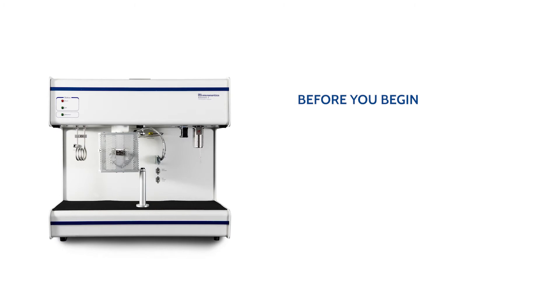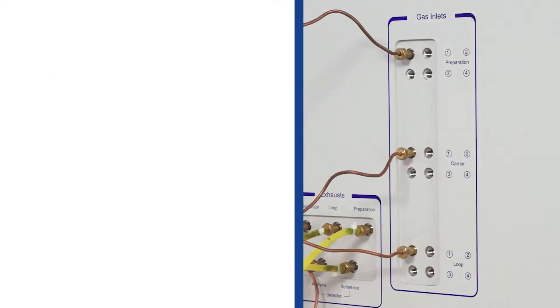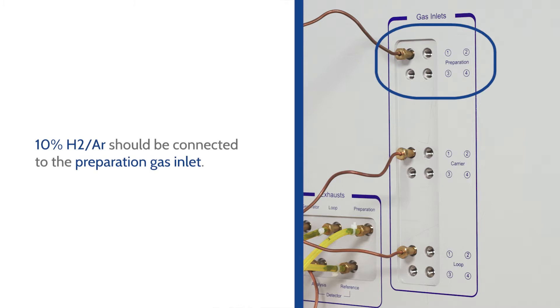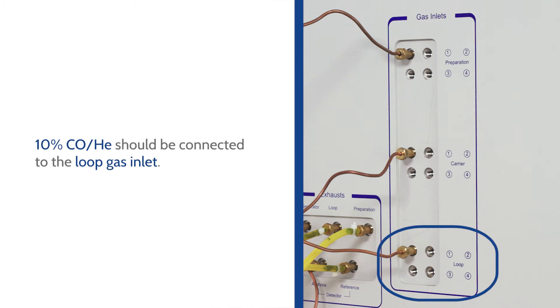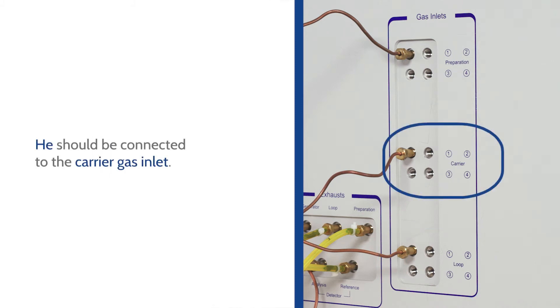There are three items that need to be completed prior to starting an analysis. First, the gases needed for this experiment are 10% hydrogen argon connected to the preparation inlet, 10% carbon monoxide helium connected to the loop inlet, and helium connected to the carrier inlet.